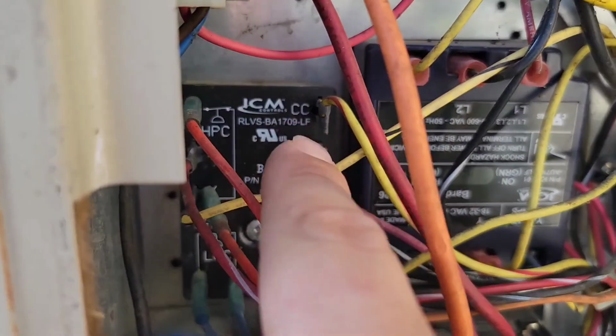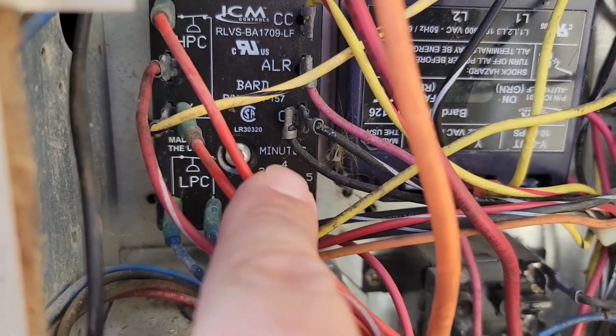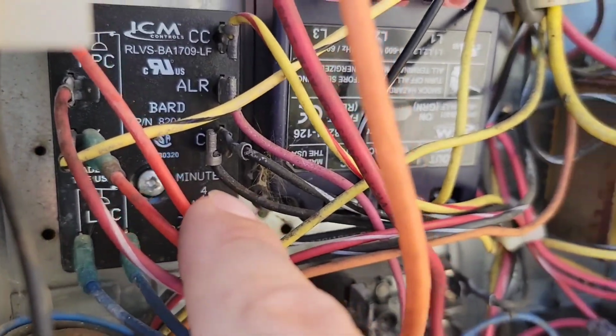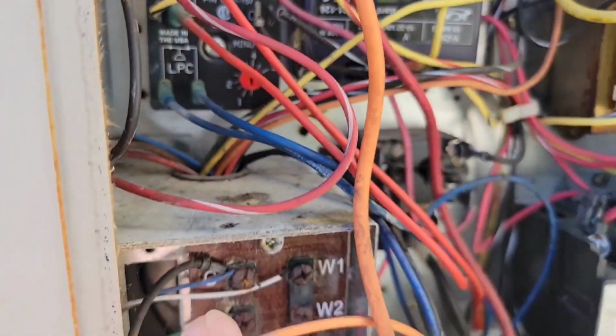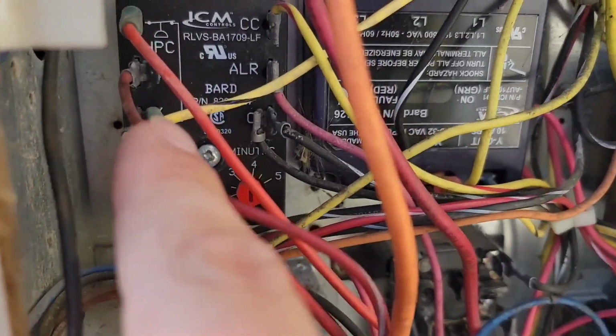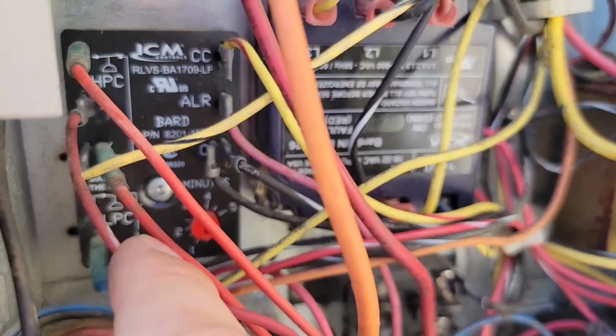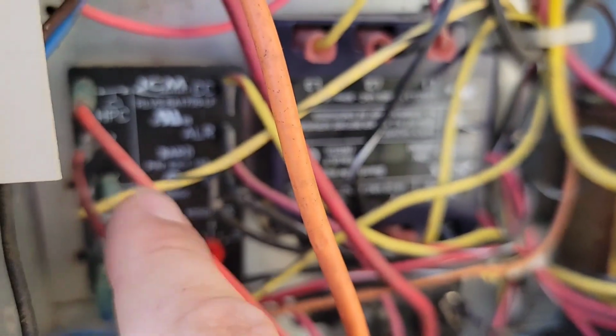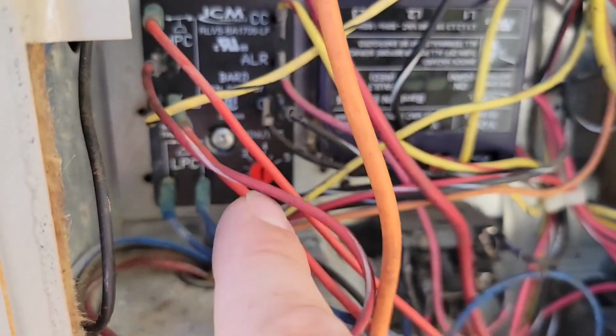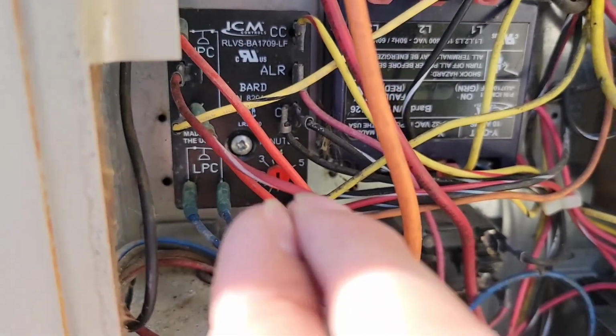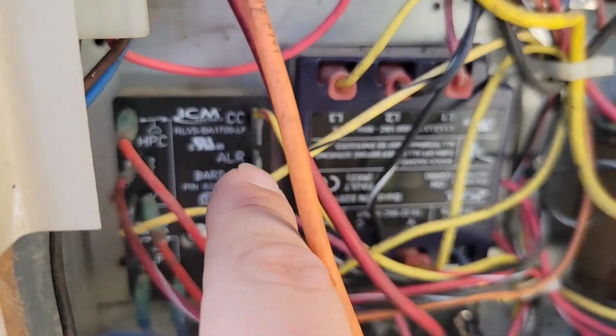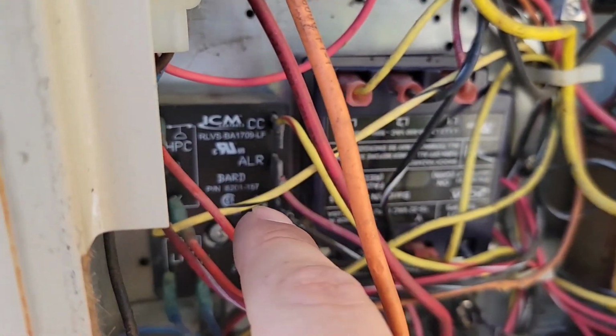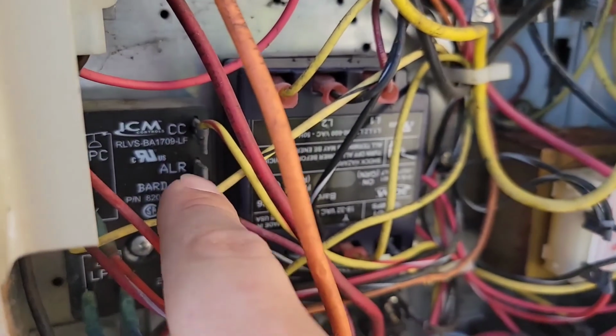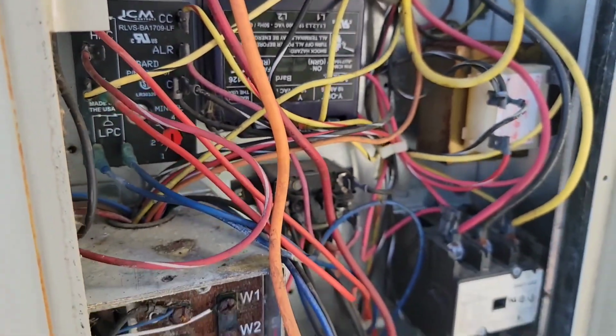You see where it says CC? Okay, contactor coil, and then C down here, this black wire. Once you check from C to right here, if it's going there, then it goes through the high pressure control right there. There's a safety, and then you got your low pressure control. It's got to be closed as well, and then it's going to come out of the CC, and it's going to send voltage to the contactor coil.